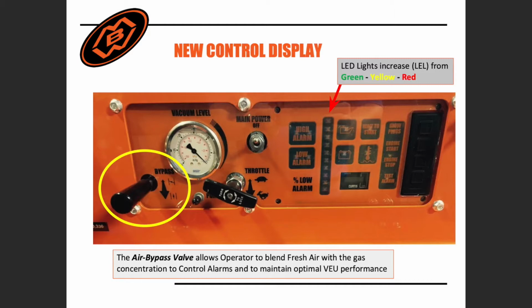This display shows the air bypass valve circled in yellow. This valve allows operators to blend fresh air with gas concentration to control the alarms and maintain optimal performance. The LED lights increase from green to yellow to red. This movement correlates to the LEL levels the sensor is detecting in real time.